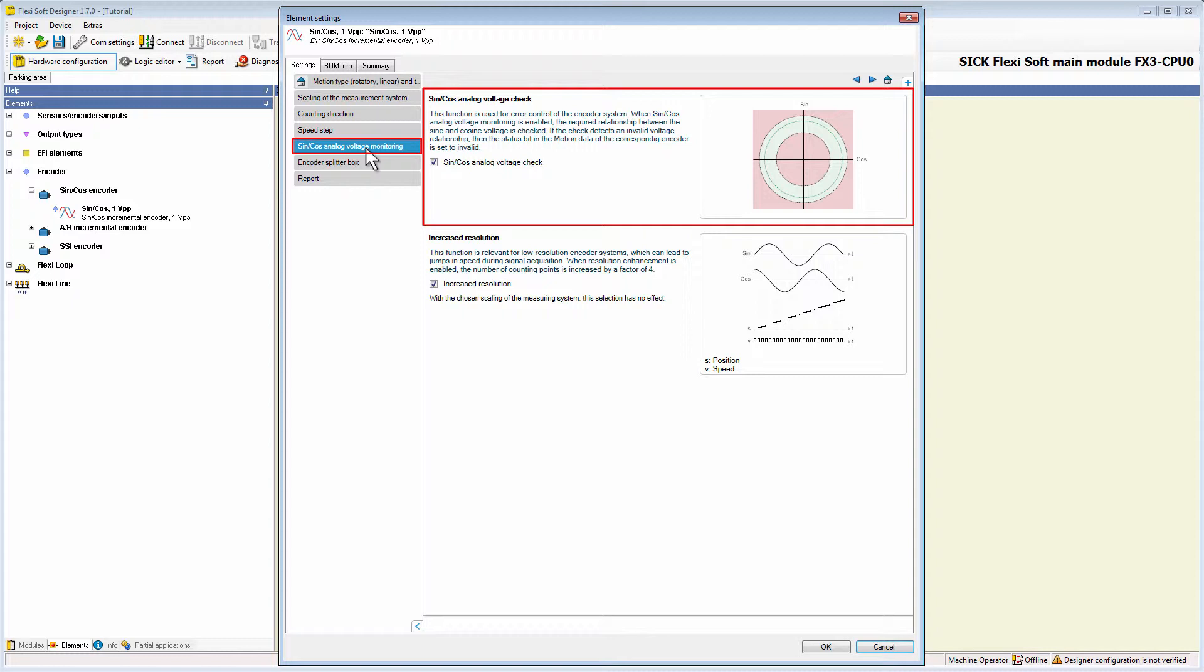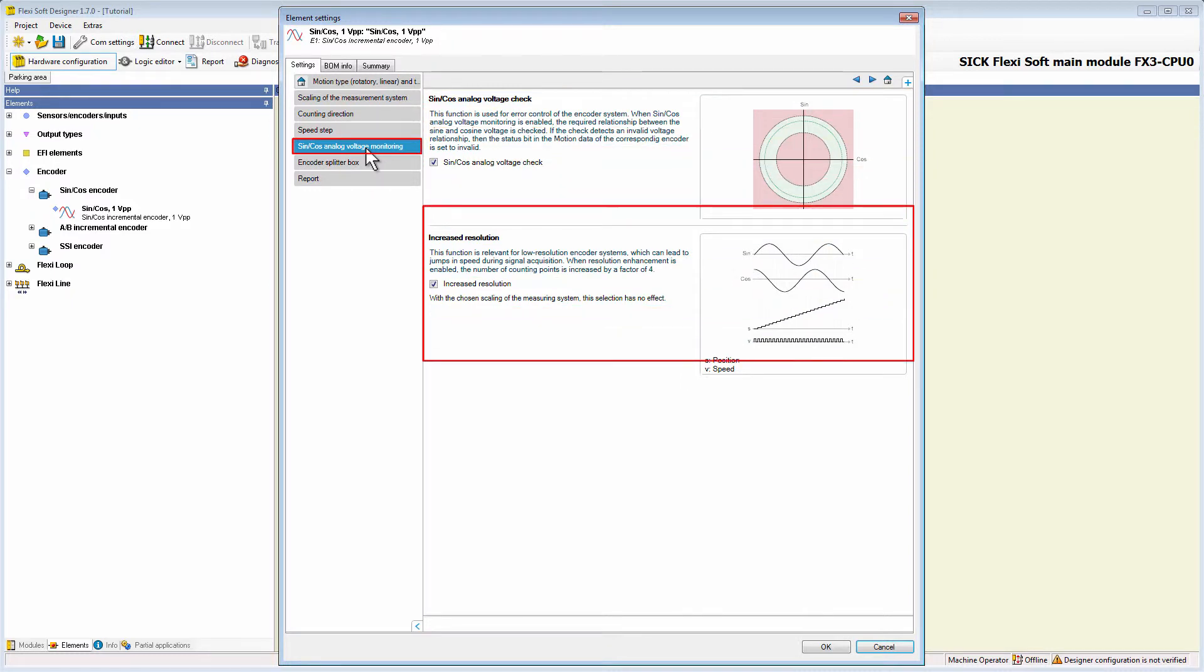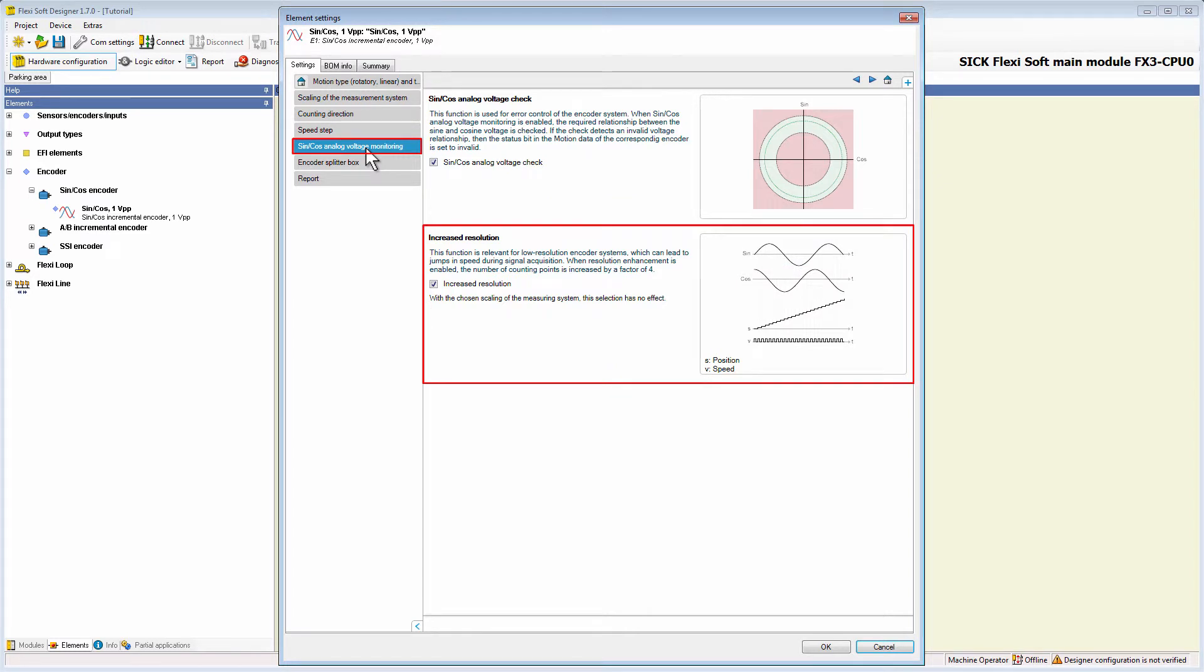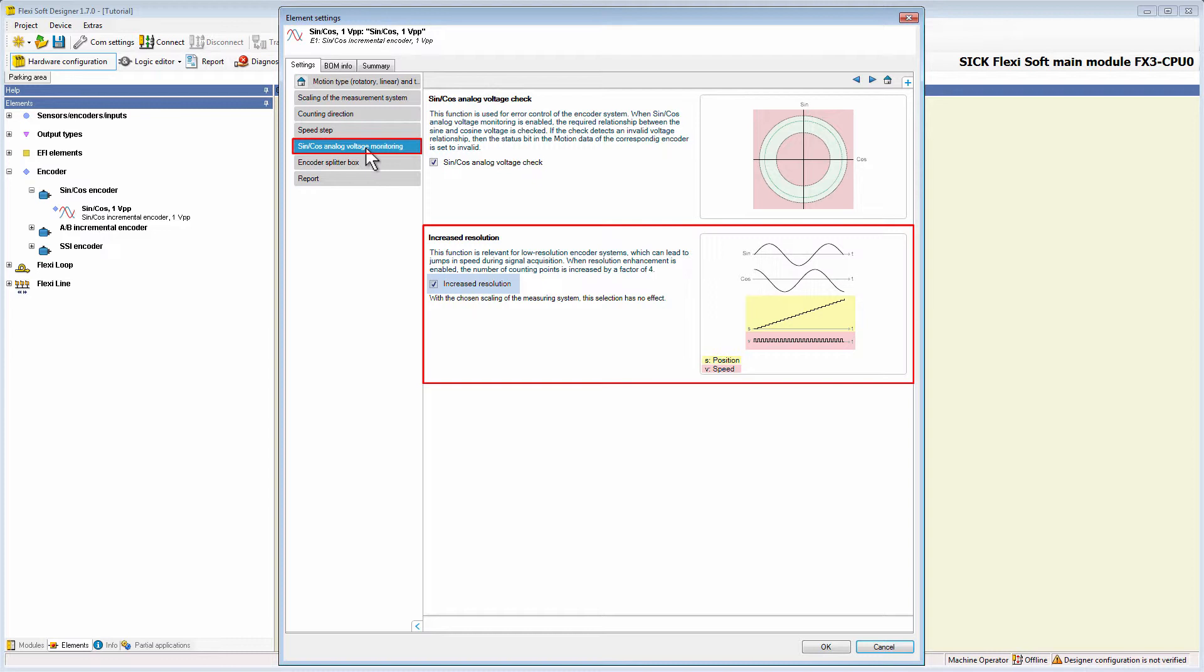Furthermore, there is the function increased resolution, which is especially relevant for low resolution encoder systems. The low resolution can lead to jumps in speed during signal acquisition. By activating the option, increased resolution, the number of counting points is increased by a factor of 4.